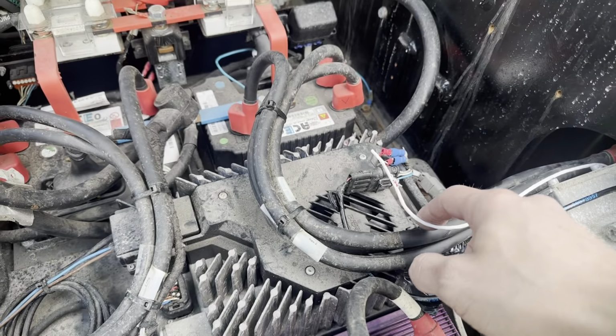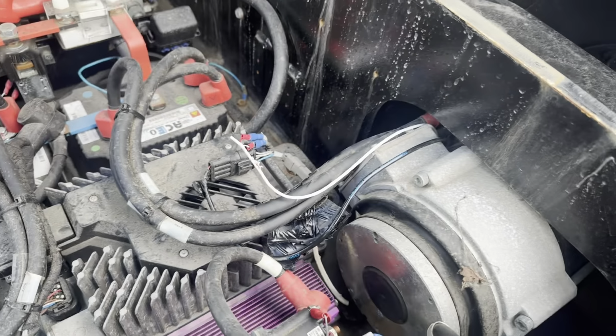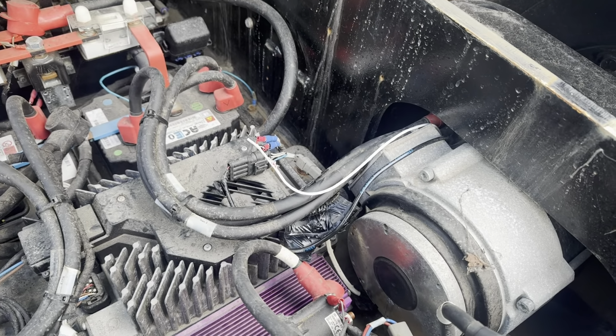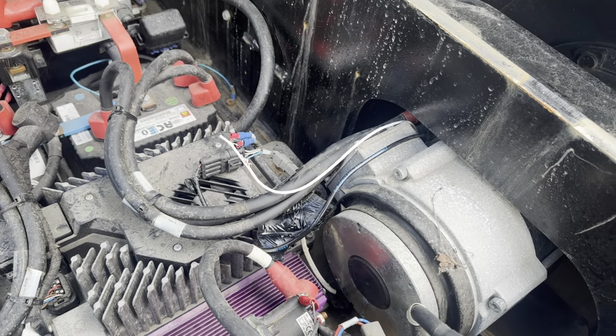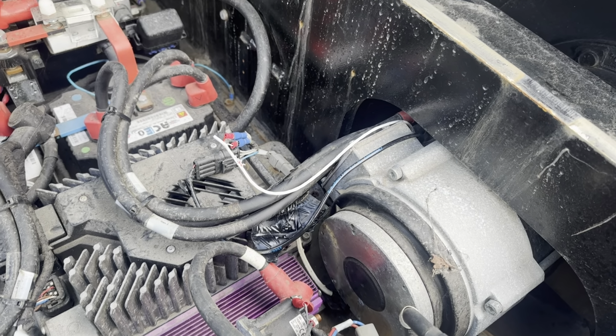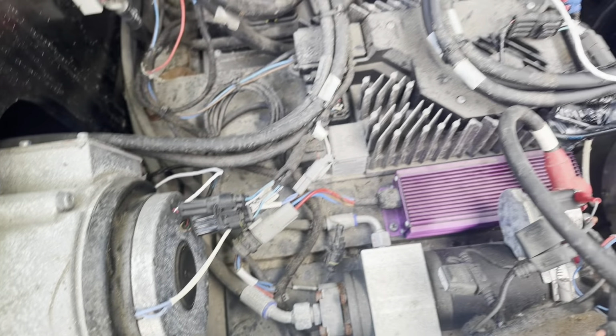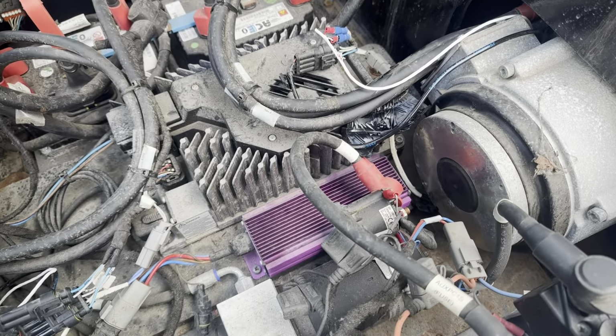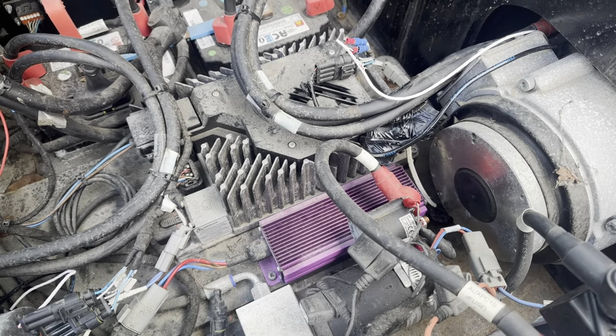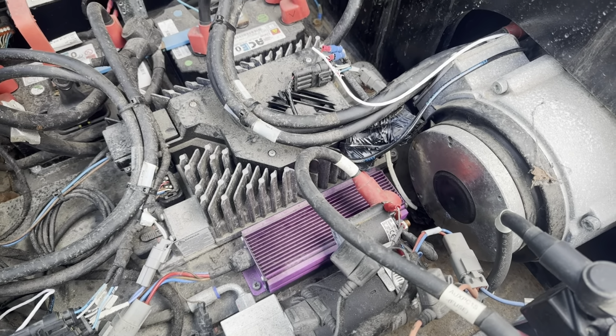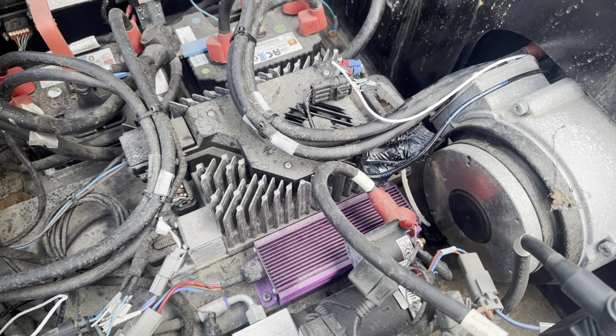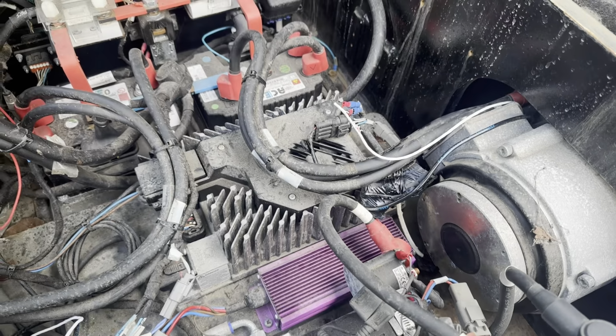Measuring resistance here on the cable, I'm getting 520 ohms, which is about right because that's what you'd expect. Resistance here is the same, 520 ohms, and it's about 10 degrees outside, so that's around where it should be. So the resistance is good, and the temperature sensor I think is good.